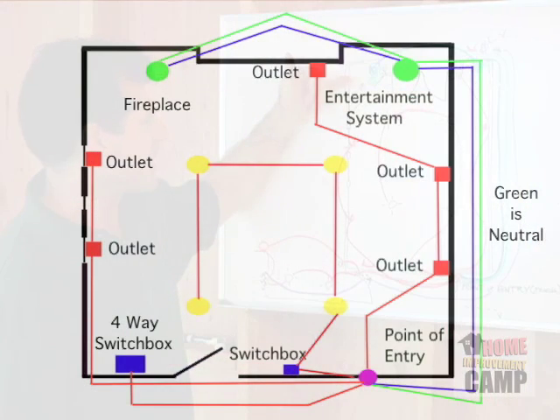The fireplace is a dedicated appliance circuit. It's not going to require the arc fault circuit interrupter, but you may want to check the codes in your area - you may want to talk to the inspector in your area because he could require it.